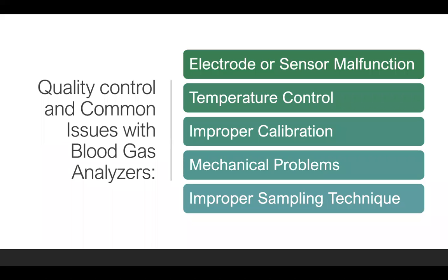Some common issues that we run into with blood gas analyzers can cause an issue with quality control. These can include electrode or sensor malfunctions. This can be caused by protein that gets deposited onto the sensors, and we can clean that off. We also want to make sure we have adequate temperature control. So a failure to maintain 37 degrees Celsius in the measuring compartment, or thermometer inaccuracy, could cause our ABG results to be inaccurate.